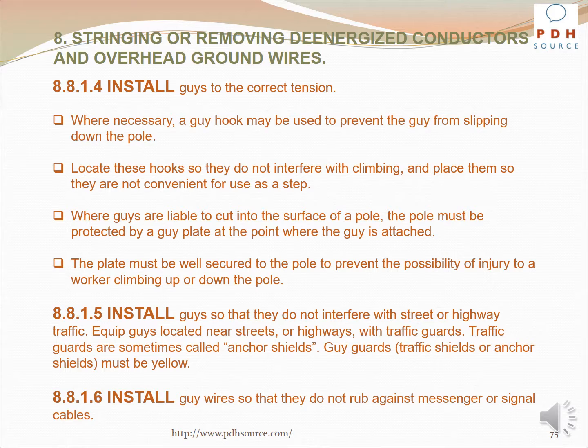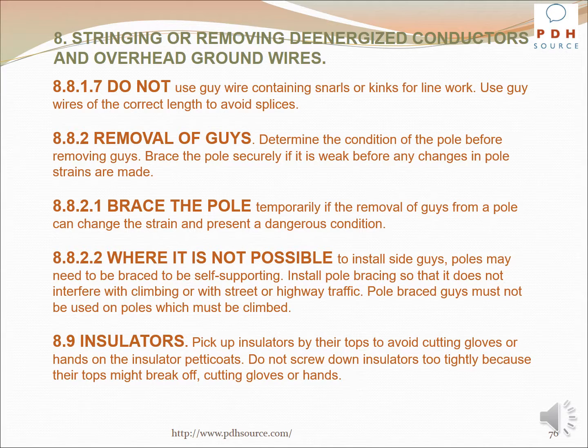Install guys so that they do not interfere with street or highway traffic. Equip guys located near streets or highways with traffic guards. Traffic guards are sometimes called anchor shields. Guy guards, traffic shields, or anchor shields must be yellow. Install guy wires so that they do not rub against messenger or signal cables. Do not use guy wire containing snarls or kinks for line work. Use guy wires of the correct length to avoid splices.